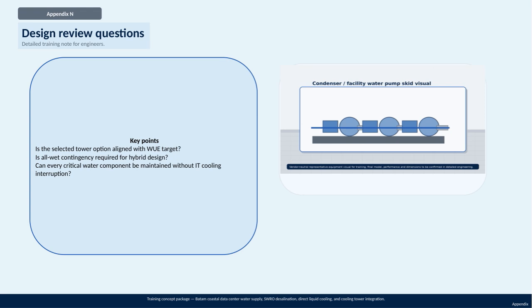First, we need to ask if the selected cooling tower option meets the water use efficiency target. This ensures that the design is sustainable and efficient in terms of water consumption. Second, we must determine if an all-wet contingency is necessary for the hybrid cooling design, which affects how the system manages different cooling scenarios. Lastly, it's crucial to verify that every critical water component can be maintained without interrupting IT cooling operations. This ensures continuous system reliability and uptime for the data center. These questions aim to guide engineers through a thorough review process, ensuring the design is both effective and resilient.